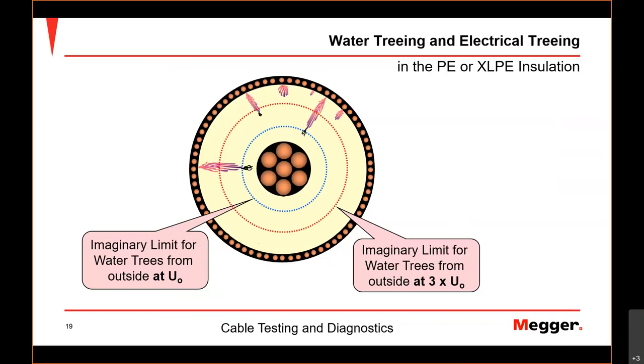Medium voltage cable, rule of thumb, you could say, has 0.2 microfarads per kilometer. So that's 25 kilometers in that case for plastic cables. And it has 0.3 microfarads per kilometer for paper cables. Paper cable has more capacity, so you can test less length, about 1/3. So a good number of kilometers you can test with VLF.